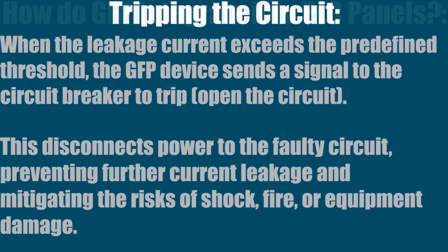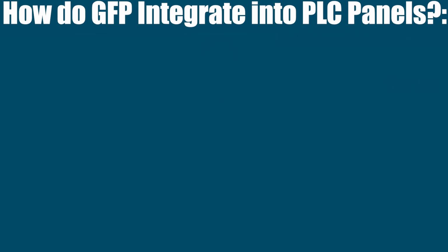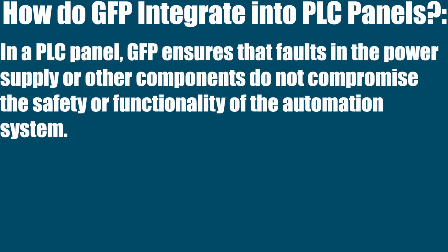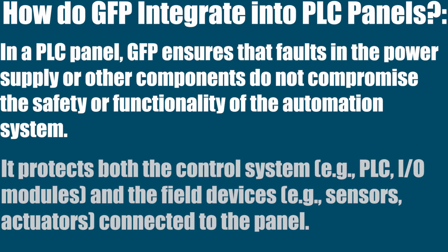How does ground fault protection integrate into PLC panels? In a PLC panel, GFP is going to ensure that faults in the power supply or other components do not compromise the safety or functionality of the automation system. It protects both the control system, whether it's a PLC or input-output modules, and the field devices like sensors or actuators that are connected to the panel.